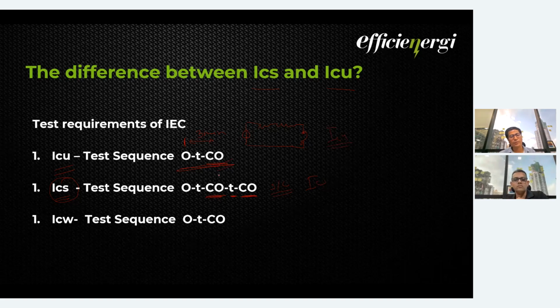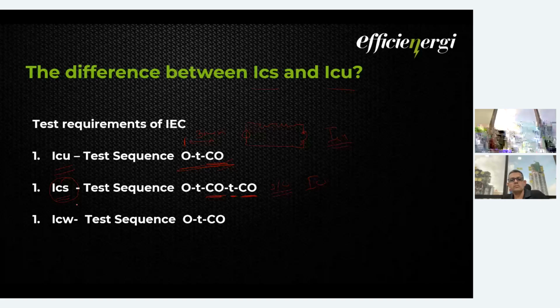After one-time fault clearing, the breaker obviously should have no damage, but it is not expected to be put into service again. But if your fault current is less than ICS, then your breaker is expected to take the operation and be brought back into service again.